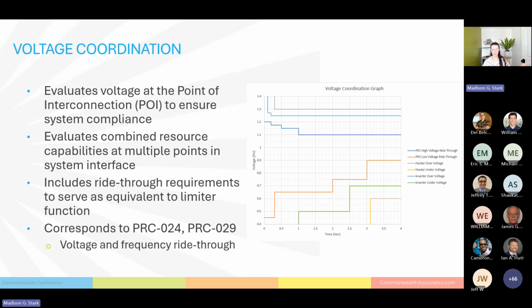So the first things that you want to hit for an inverter are your voltage ride-through requirements. These are designated requirements that your inverter has to be able to ride through. These are voltage events. The voltage in the system goes high, the voltage in the system goes low. The inverter has to be able to continue to push power in these events. So here, when we go up, we see this high voltage ride-through line with no intersection. Fantastic. The next thing we want to see is the inverter protection itself. This is that inverter internal control that's limiting the inverter's behavior. Perfect. And then outside of that, we want to see our feeder protection. This is our system protection. This is our big overarching protection. We want that to be the last thing to go, because that's kind of plant shutdown criteria. That's going to stop all connection to the grid. That's what's going to shut our plant down. And we want that to be the last thing to act. So here we see no intersection. That's our last thing. Great. On the high side, this is appropriately coordinated.